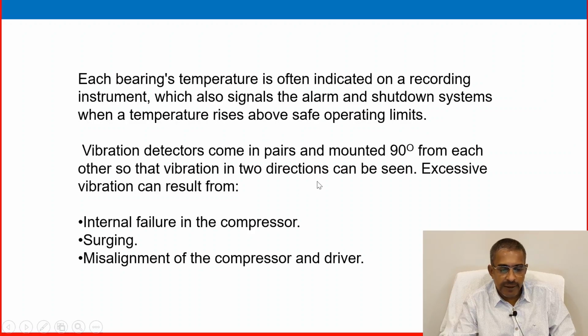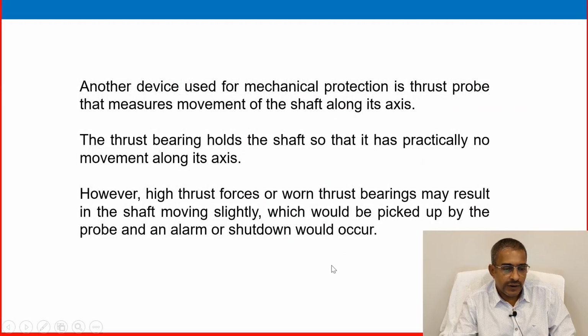Vibration detectors come in pairs and are mounted 90 degrees from each other so that vibration in two directions can be seen. Excessive vibration can result from internal failure in the compressor, surging, or misalignment of the compressor and driver. Another device used for mechanical protection is the thrust probe, which measures movement of the shaft along its axis. The thrust bearing holds the shaft so that it has practically no movement along that axis. However, high thrust forces or a worn thrust bearing may result in the shaft moving slightly, which could be picked up by a probe, and an alarm or shutdown will occur.